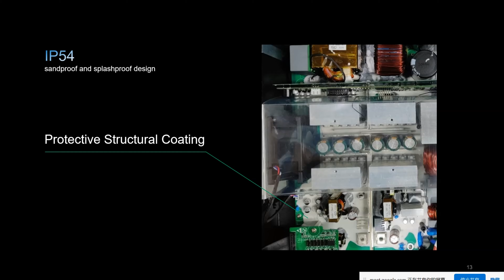On the side of the inverter, we designed it with a double layer filter, which can efficiently prevent big sand and middle-sized sand from entering the inverter. For the parallel connection, you can connect them in single phase AC output or 3-phase AC output.